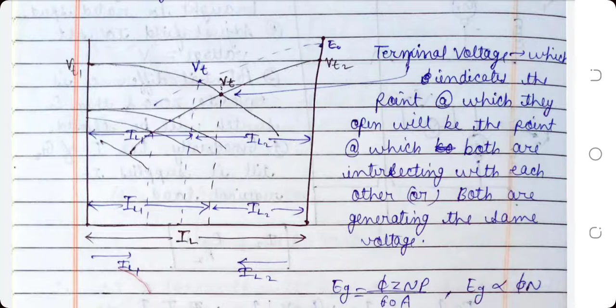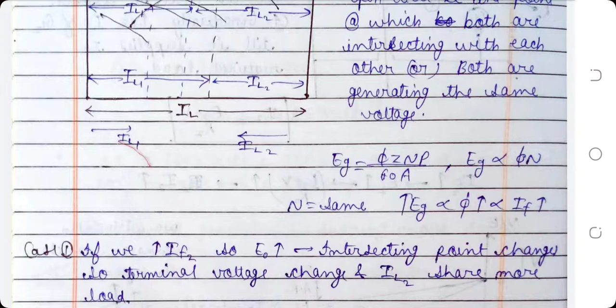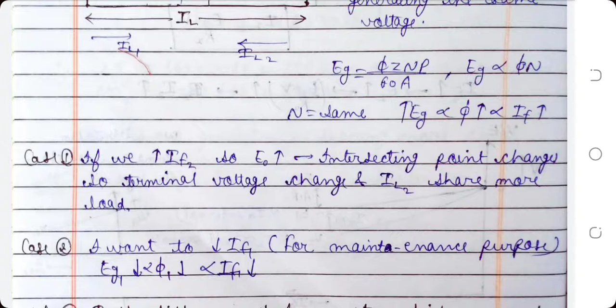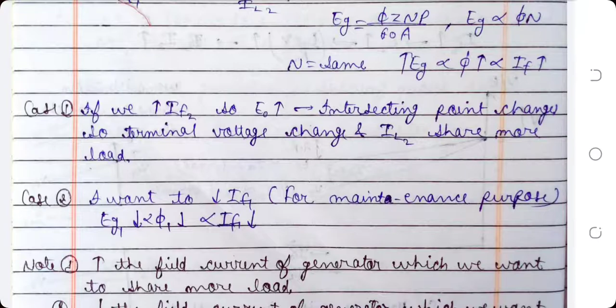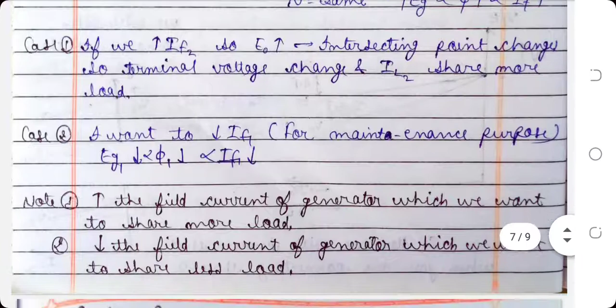So generated EMF Eg equals phi Z N P upon 60A. So Eg is proportional to phi into N. Because N is the same, if Eg increases, then IF increases. So case first, if field current IF2 increases, E0 increases, the intersecting point changes, so the terminal voltage and load current IL change, and it shares more load. And the second case is, if IF2 decreases for maintenance purposes, then Eg1 decreases, so flux of 1 decreases, and field current of 1 also decreases.